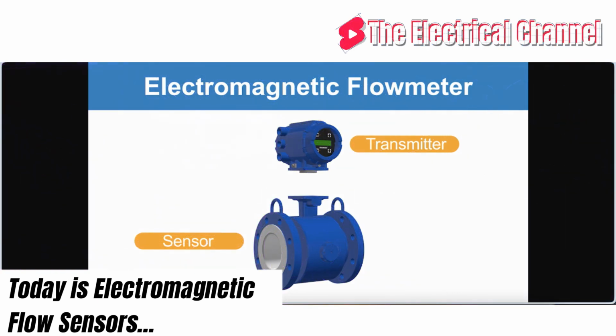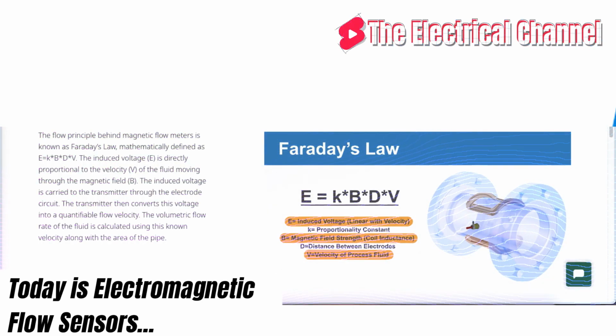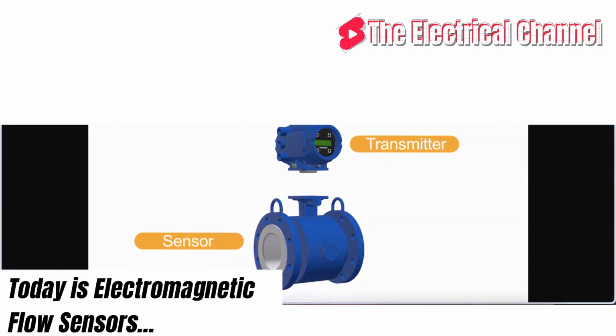So what's behind the measurement of flow sensors? The measurement principle states that Faraday's law of induction states that a metal rod moving in a magnetic field induces electrical voltage. This dynamo principle also governs the way electromagnetic flow meters work. As soon as the electrically charged particles cross the artificial magnetic field generated by two field coils, an electric voltage is induced.